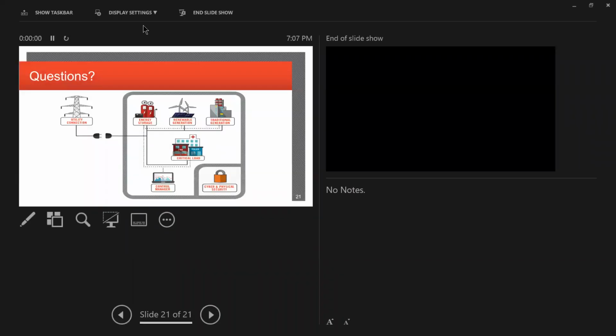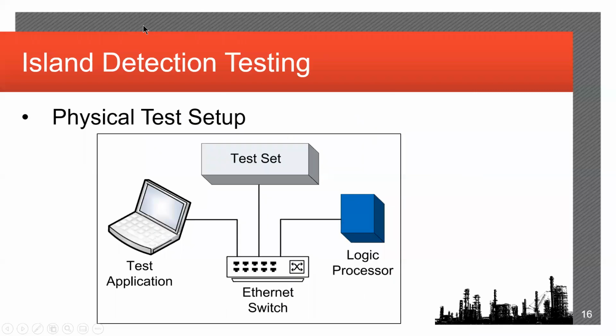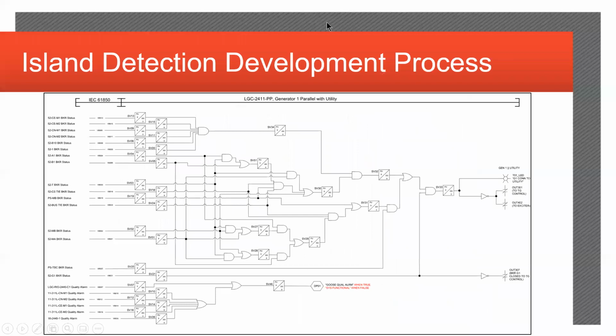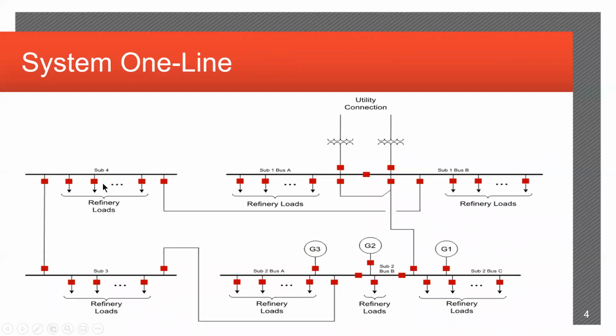I'll go back to the single line diagram, and talk a little bit about the history we had here. For this main PDC, the sub 4 PDC, and the sub 3 PDC, Power Engineers were deeply involved with the design, installation, testing, relay settings, SCADA implementation, networking, fiber design, all sorts of things. They're relatively modern, all installed in the last 8 years, I think. Down here at this power plant, this thing's a Jurassic monster. It has been around for 60, 70 years.